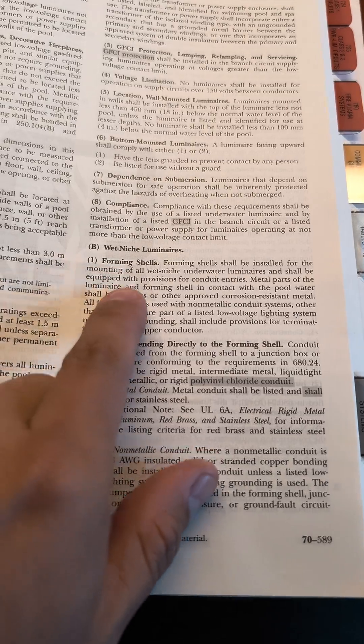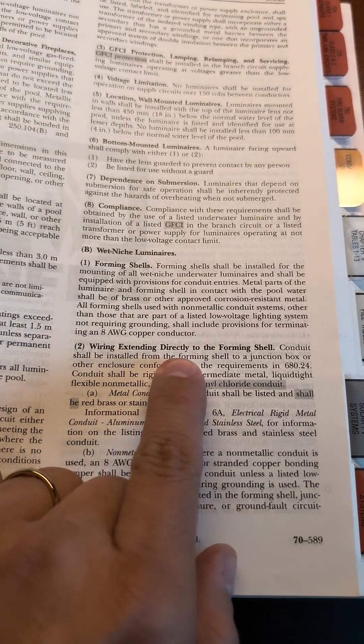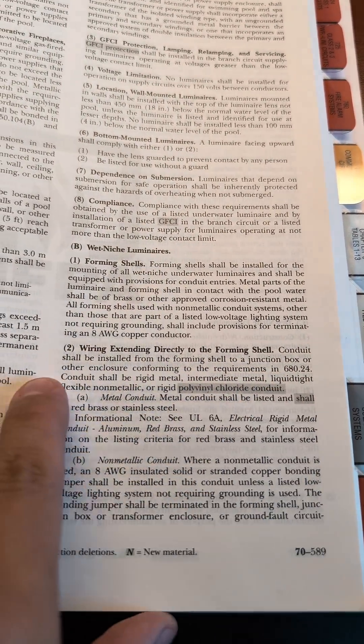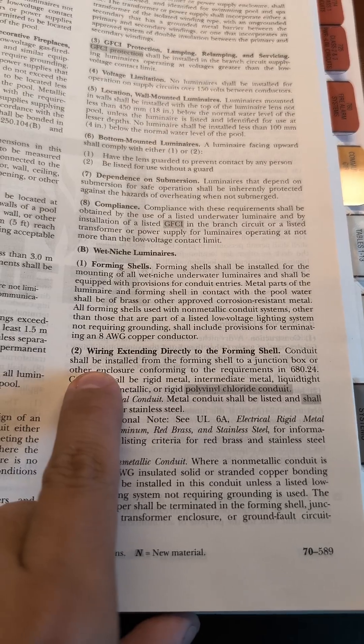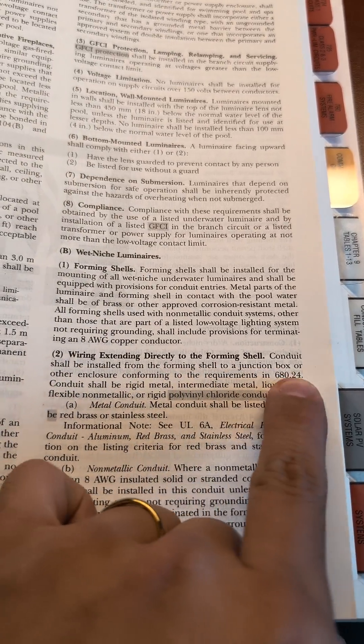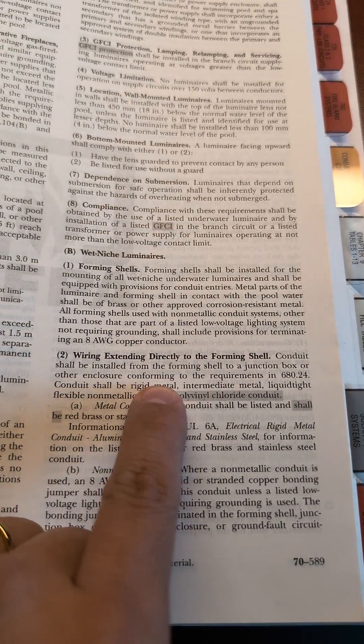To the forming shell. So conduit shall be installed from the forming shell to a junction box or other enclosure conforming to the requirements of 680.24.